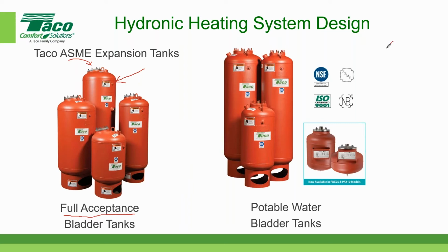And then I also wanted to show everyone, even though today we're not talking specifically about potable water systems, that we make a full line, including these small tanks, we call them micro tanks, for potable water systems. So the expansion tanks on the right are potable water, bladder style tanks. And then the ones on the left are full acceptance bladder style tanks. The ones on the left would not be suitable for potable water. The ones on the right would be suitable for potable water. And you can see the one on the right there, NSF certified. Okay, so those are some more of the components that go into an HVAC system. Let's continue.